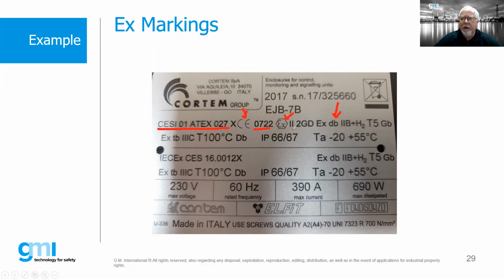So this is our ATEX marking string. We have surface area, category 2G and D, so it's good for zone 1 and zone 21 based upon both gas hazards and dust hazards. Our EX marking string, which is flame-proof. In this case, it's telling us it's good for 2B gases plus hydrogen. So it's not 2C, but it's 2B plus hydrogen. So in effect, this product was not able to pass the requirements for acetylene, but it did pass the requirements for hydrogen. Then we have a T code associated with it, T5, meaning that the relevant surface area for this product will never exceed 100 degrees C. And then finally, our EPL GB.